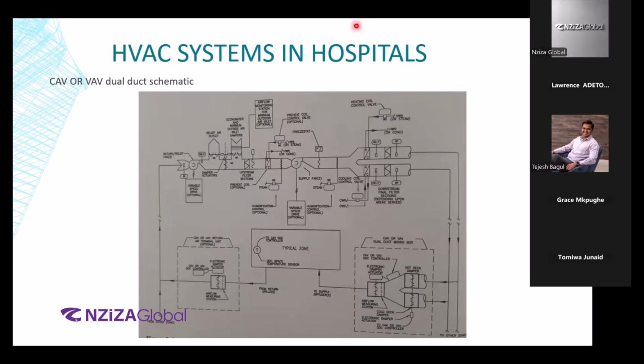When specifying an air handling unit, you will also see a total static pressure available for the air handling unit. That means the internal static pressure for all of these components. So when the air goes from this point to this point, this point to this point, it is encountering barriers at every point, right? Like this fan, of course, it is pushing the air, adding to the static. When it comes over here, there is a damper. The air has to overcome the resistance of the damper to move forward, right? Then we have the filters. The filters will end up using the most amount of static in the system. And the higher you go on the MERV filter rating, the harder it is for the air to go through it, right? Now going from this point to this point also has a pressure drop.